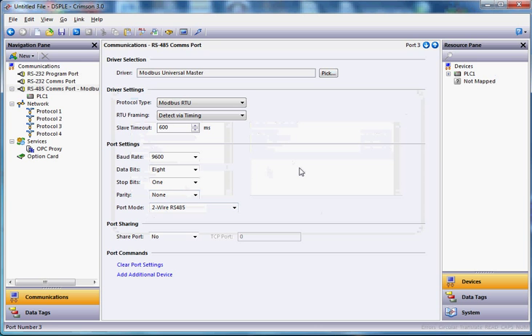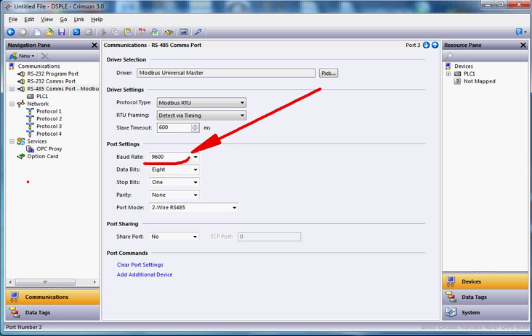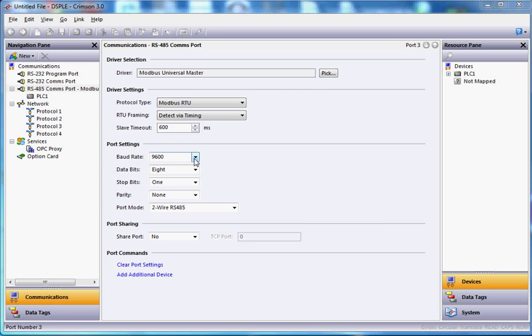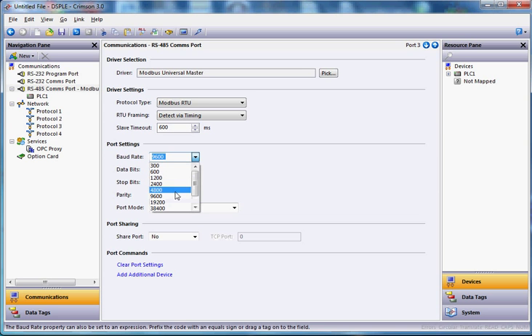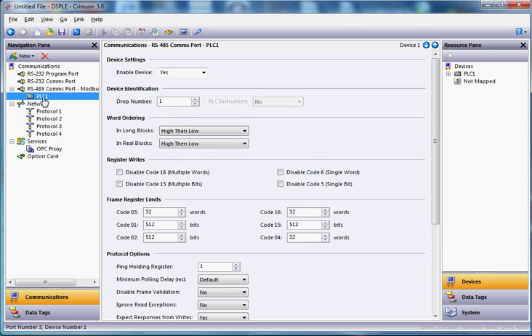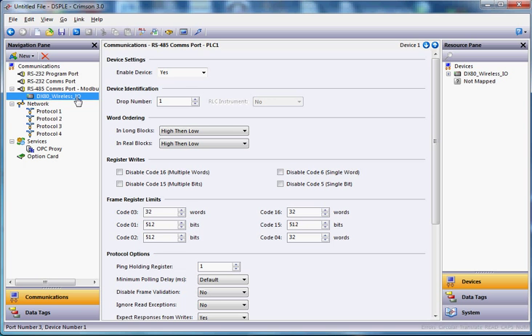And now the only thing I need to change in here is the baud rate right here. The default baud rate on all Banner wireless products is 19200. So I'm going to hit the pull down here and select 19200. And then over here on the left where it says PLC1, I might rename this DX80_wireless_IO. Alright, so that sets up that part.